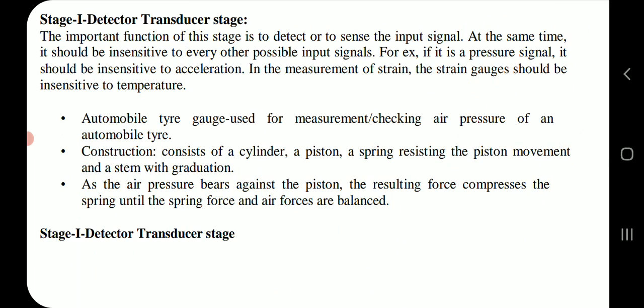Stage 1, detector transducer stage. The important function of this stage is to detect or to sense the input signal. At the same time, it should be insensitive to every other possible input signal. For example, if it is a pressure signal, it should be insensitive to acceleration. In the measurement of strain, the strain gauges should be insensitive to temperature.